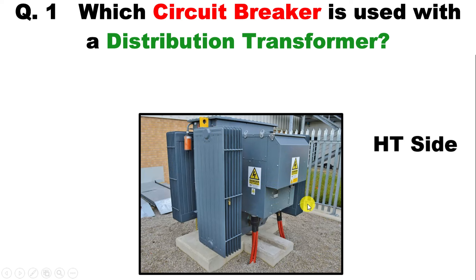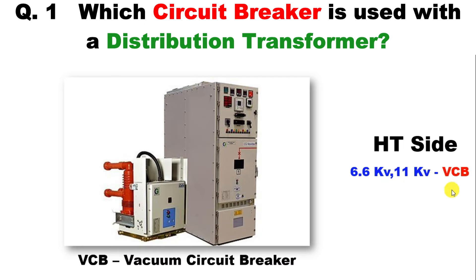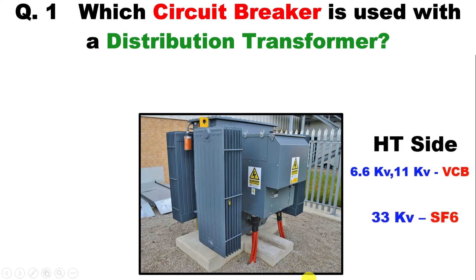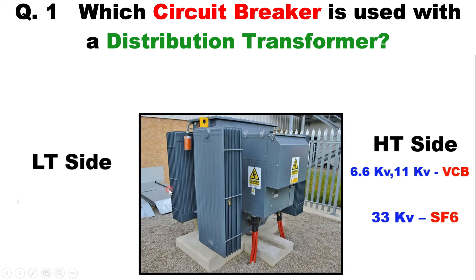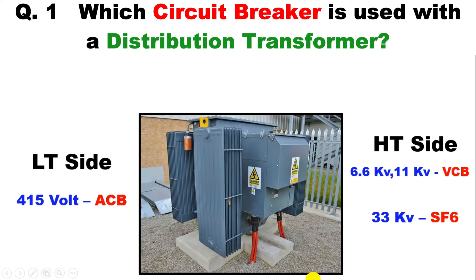The power supply given to the transformer can be 6.6 kV or 11 kV. If up to 11 kV power supply is given, we use a VCB — Vacuum Circuit Breaker. In some companies, 33 kV incoming power supply is used; in that condition we use an SF6 circuit breaker. On the secondary side, voltage is low, so we use an ACB — Air Circuit Breaker.